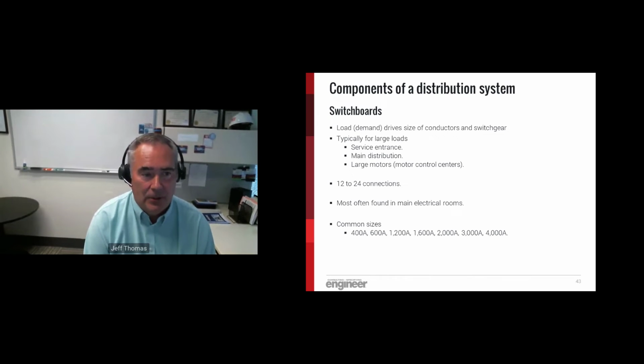So let's go a little deeper dive on some of our components. We talked about switchboards, and within our industry, there are a lot of terms that get used: switchboards, switchgear, panel boards, load centers, so on and so forth. Switchboards and switchgear sometimes are used interchangeably. Switchboards are the large items. This is where the service entrance comes in or main distribution occurs. They're typically physically large, 3 feet wide, 4 feet deep, 7 feet tall for the biggies. And then you start lining them up as you get larger and larger. Typically, there are not a lot of connections in each switchboard because these are large connections, large current capacities, so we need a lot of physical space. Typical switchboard sizes start around 400 amps and go all the way up to 4,000 amps. A 4,000 amp switchboard is not going to be a single 3-foot unit. It's going to be several units bolted together and connected with a bus, typically.